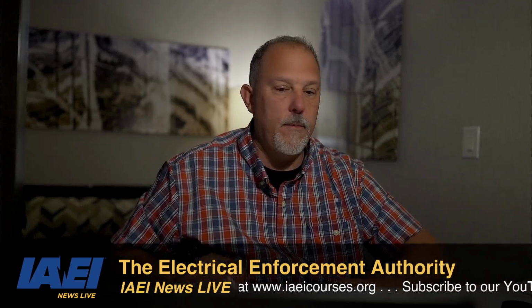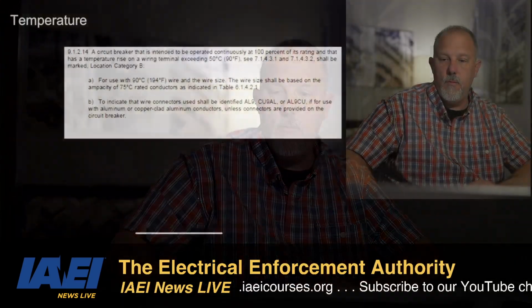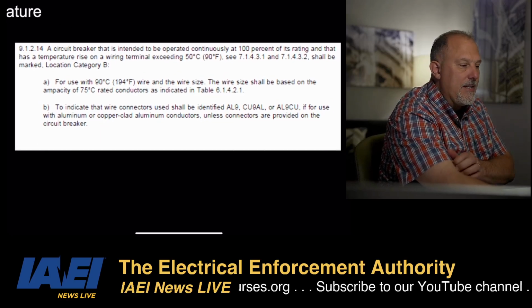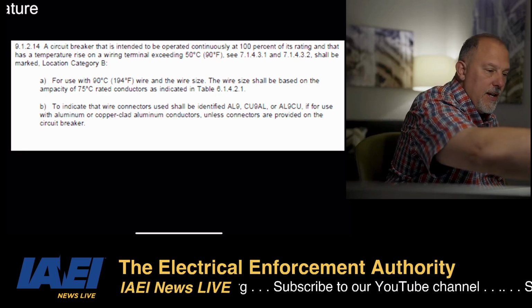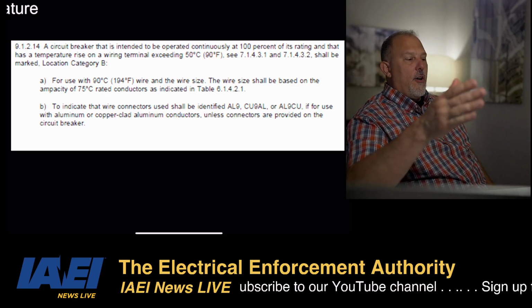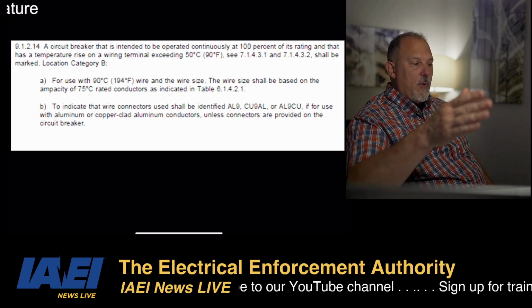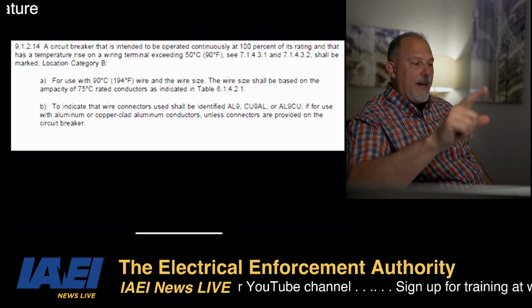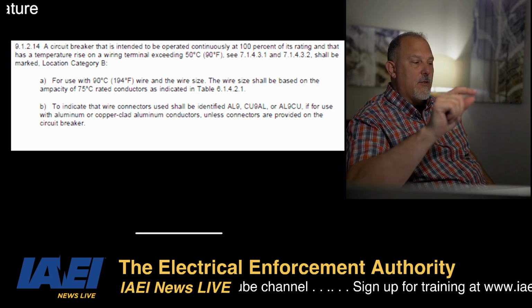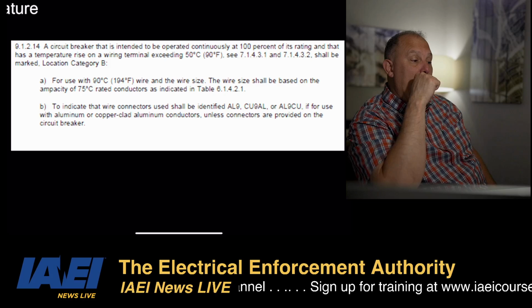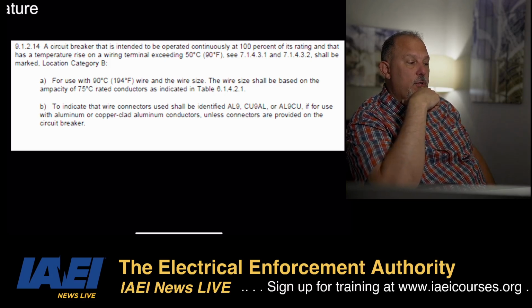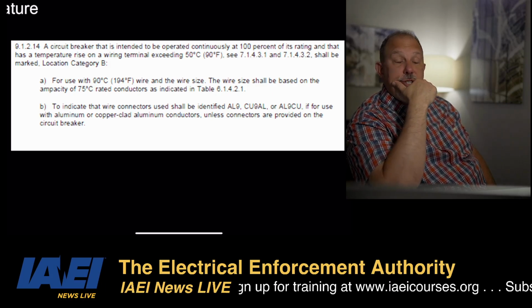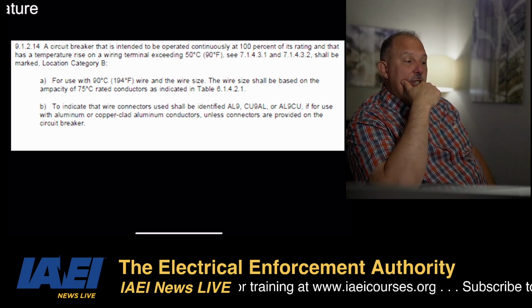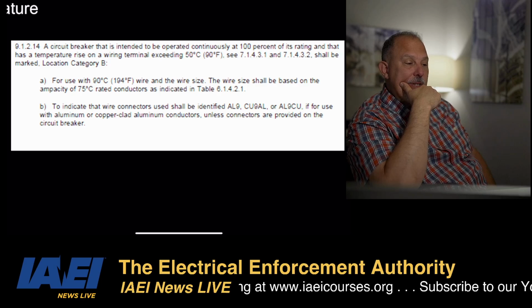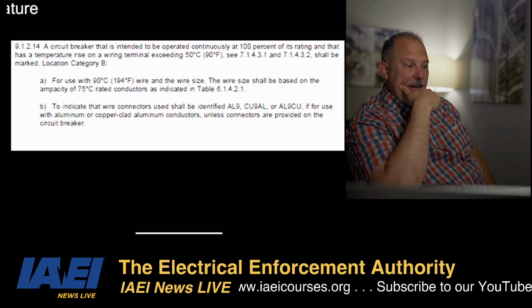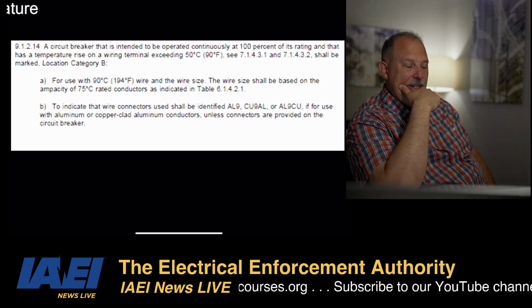So, a circuit breaker that's intended to be operated continuously at 100% of its rating and that has a temperature rise on a wiring terminal exceeding 90 degrees F shall be marked location category B for use with 90 degree C wire and the wire size. The wire size shall be based on the ampacity of 75 degrees C rated conductors as indicated in table 61421. Interesting. A circuit breaker that is intended to be operated continuously at 100% of its rating and that has a temperature rise exceeding 90 degrees.